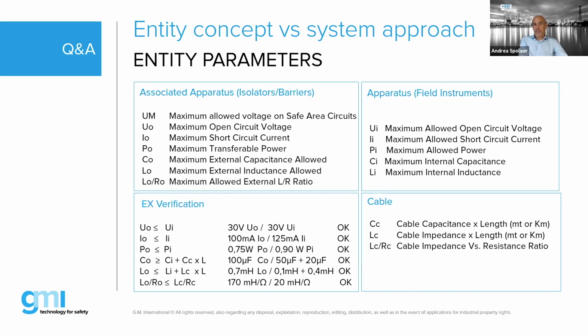You must verify that the values—especially current, voltage, and power—for the isolators are lower than the corresponding values for the field instruments, while capacitance and inductance must also satisfy certain relations. These are very important, and in the calculation, the cable parameters also have an effect, since cable length greatly influences the values for capacitance and inductance.